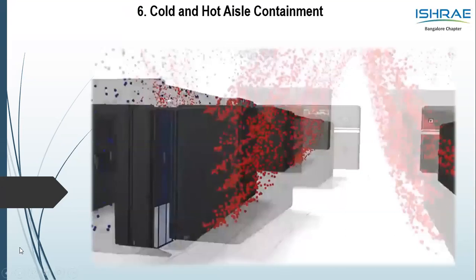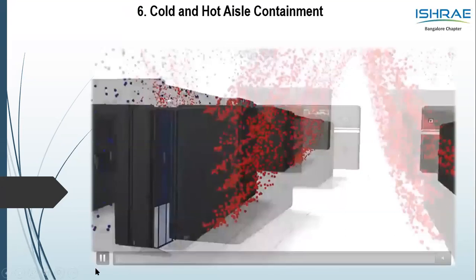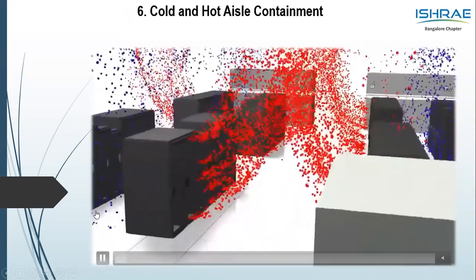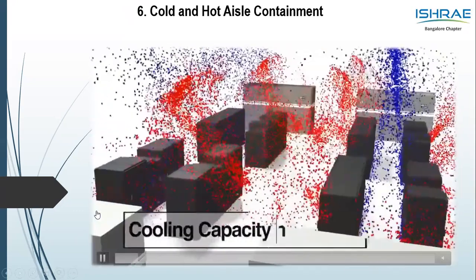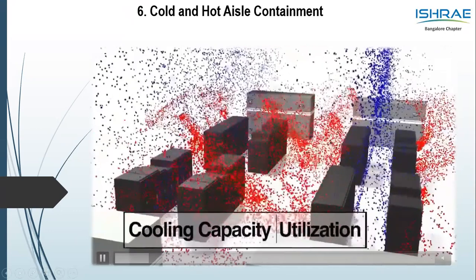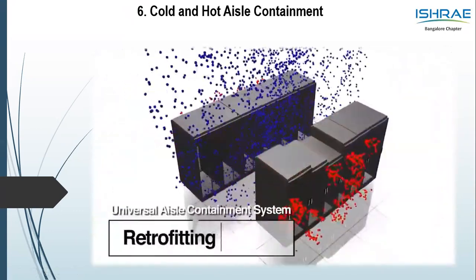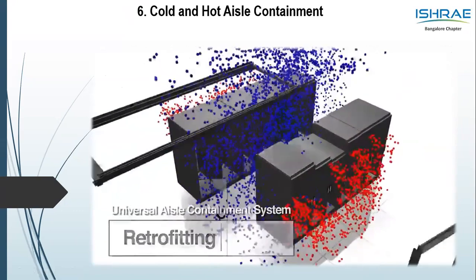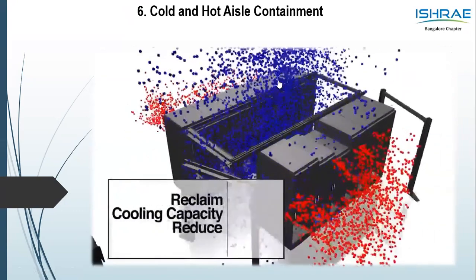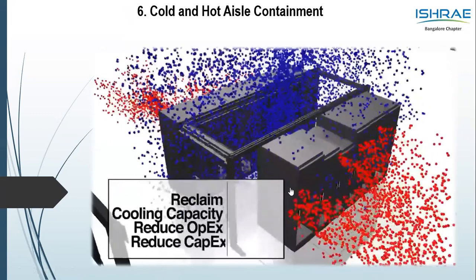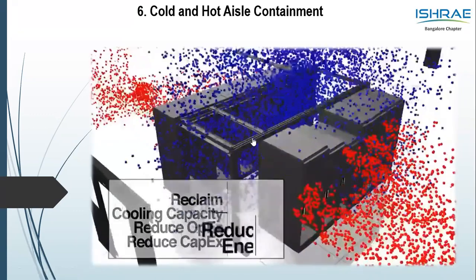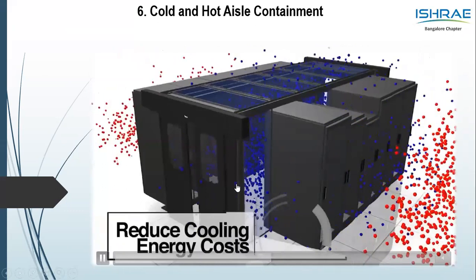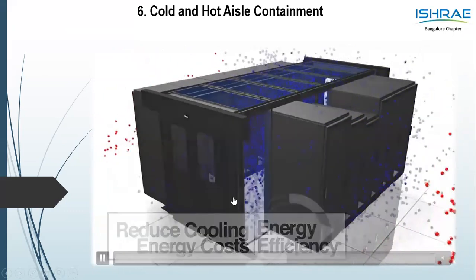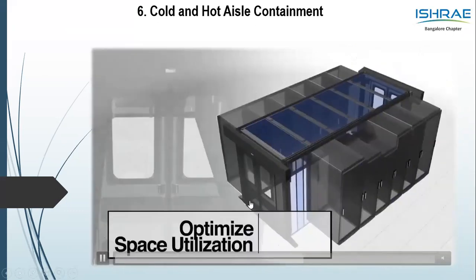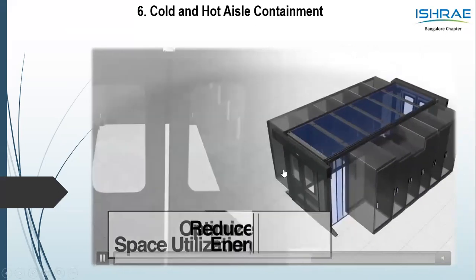So from there, we look at the containment. Very important is that we might have the best CCU and have placed it well, but what happens in the data center if we don't have containment, let's say 10, 20, 30, 40 racks? When we place these racks, there can be a mixture of the cold air and the hot air. Thereby, the containment is very important. This is a video of a cold aisle containment. You save close to 30 to 40% when you have a containment. Just a video of a cold aisle containment.